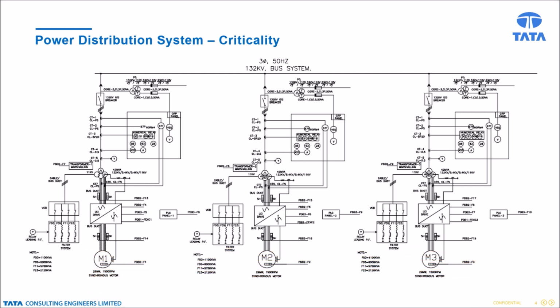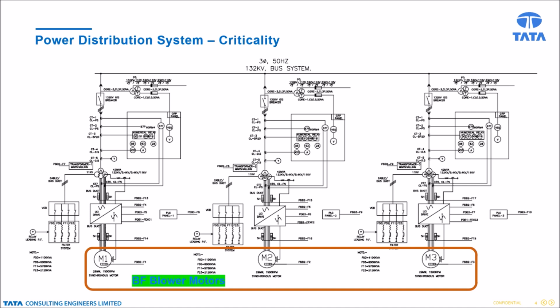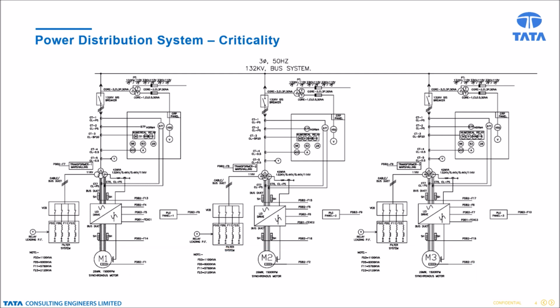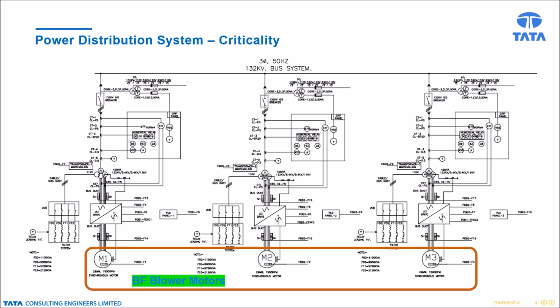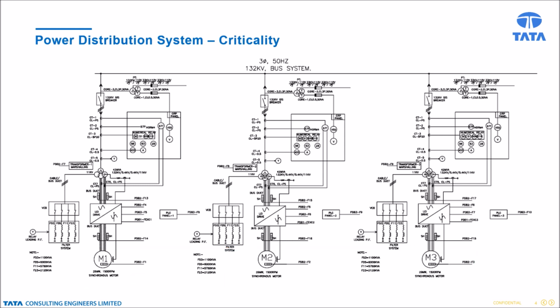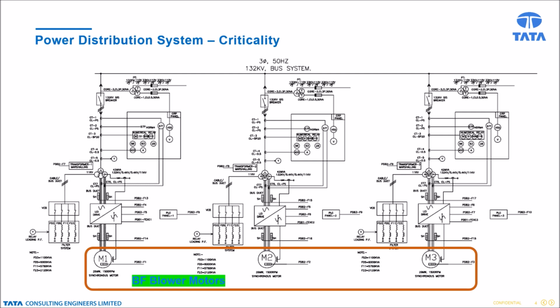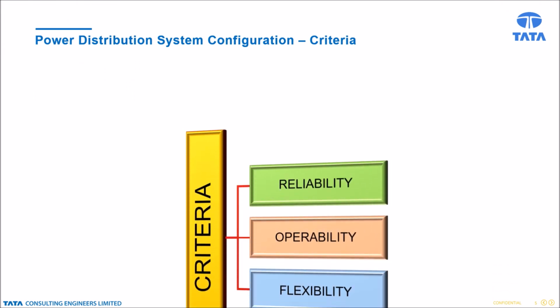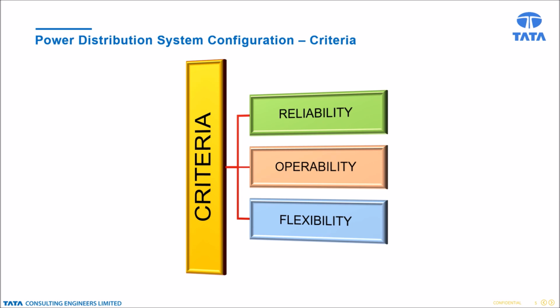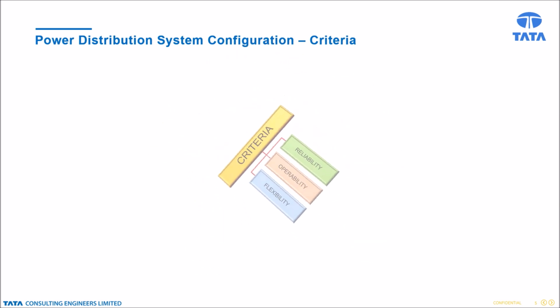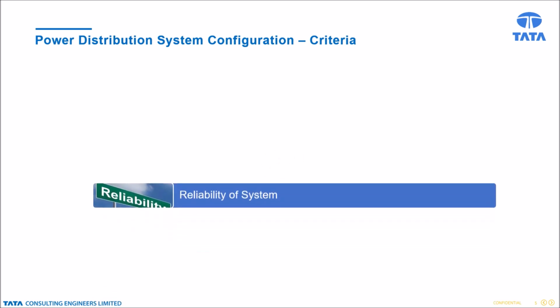As an example, interruption of power supply to blast furnace blowers or failure of blast furnace blowers may cause capital damage to the blast furnace, putting the steel plant operation into complete halt. Recovery time also is quite high as manufacturing and refractory work of capital equipment demand long delivery time. Hence, if electrical power driven blowers are envisaged, 3 x 50% configuration is more beneficial from reliability point of view. Criticality aspects of reliability and flexibility of power distribution network along with power sourcing require formation of robust power system that will enhance safety of capital equipment. From the feasibility of capex, optimization of power network needs to be looked into as well.